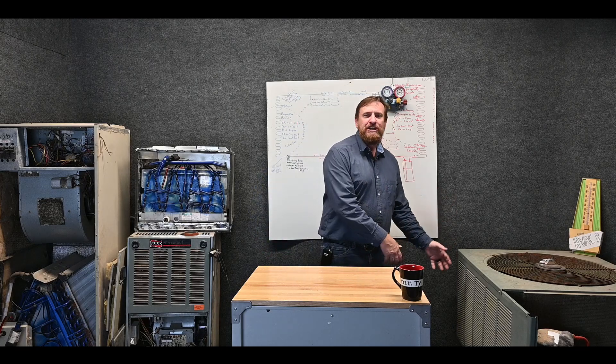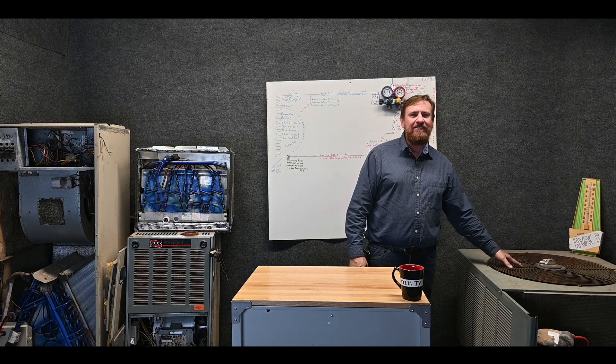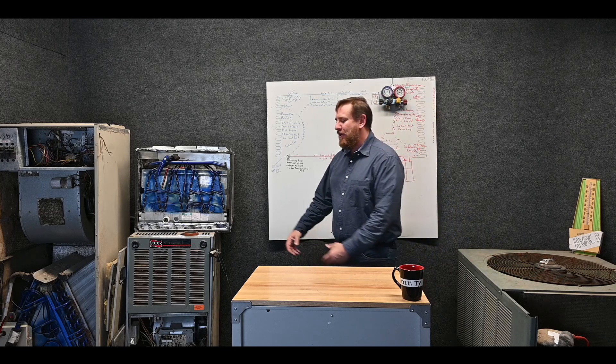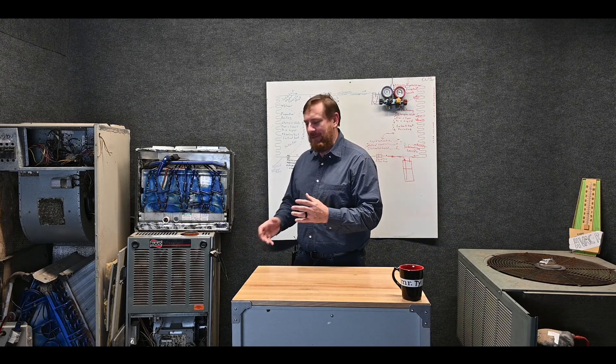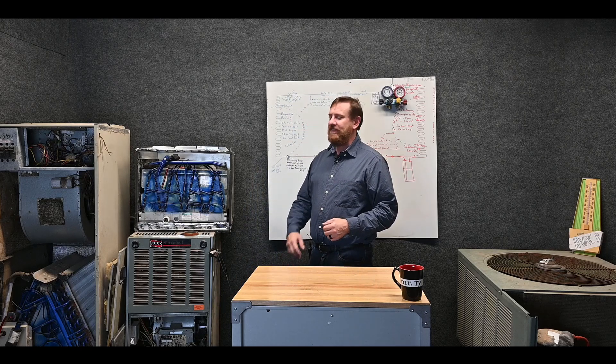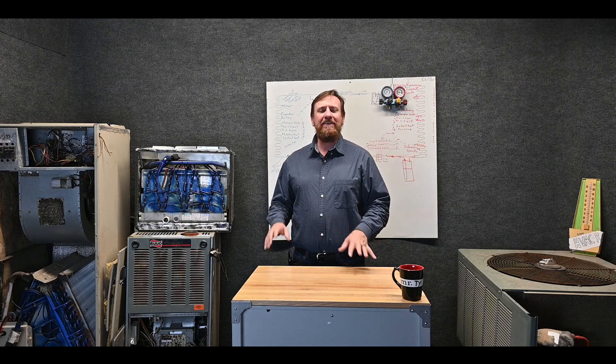So I went outside, I washed out the condensing unit, got this filthy, got all the dirt cleaned out of it, got the leaves cleaned out of it, even cleaned the fan blade, polished the unit up, made it nice, pulled the blower out, pulled the wheel, cleaned it, put it all back together, put it in, put in a brand new filter, made sure that filter wasn't restrictive, and everything looks good. I start the system back up and everything starts running.